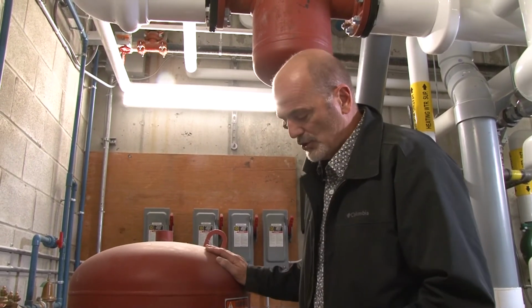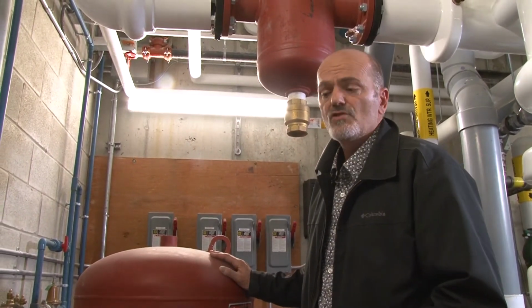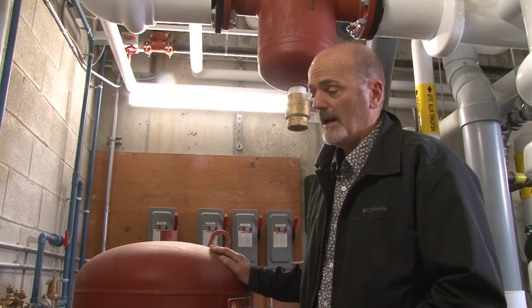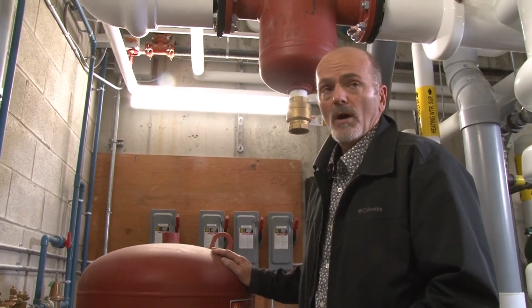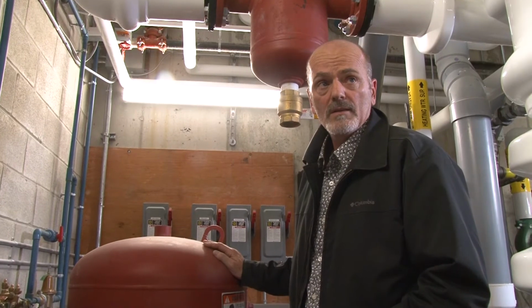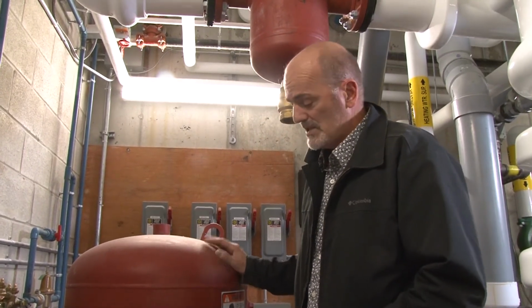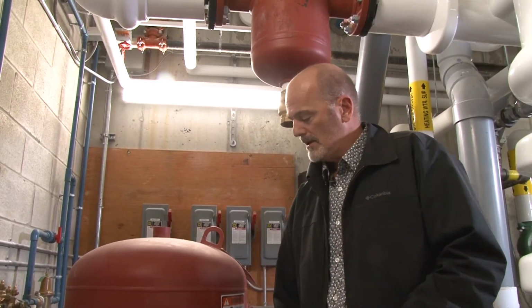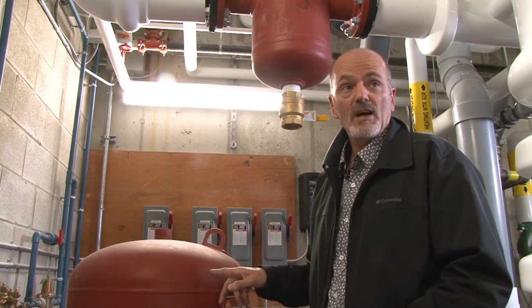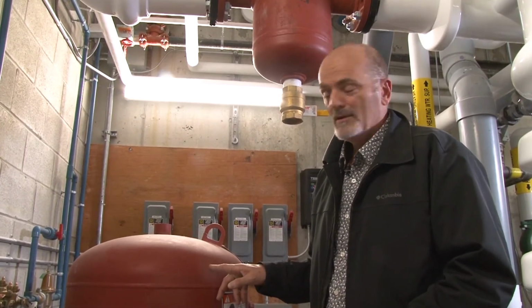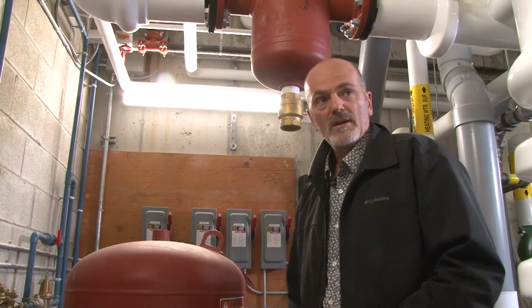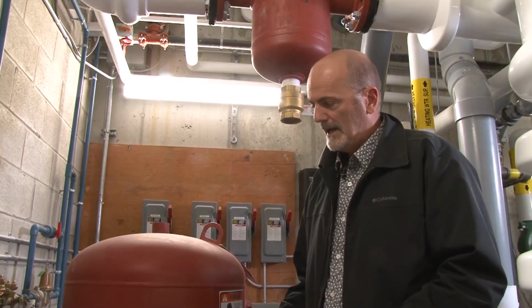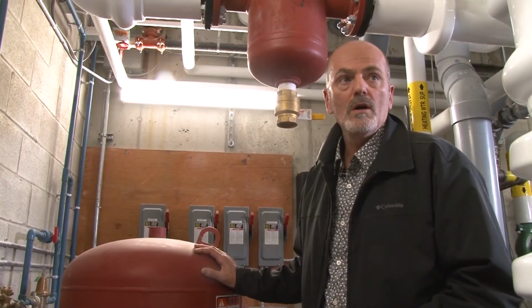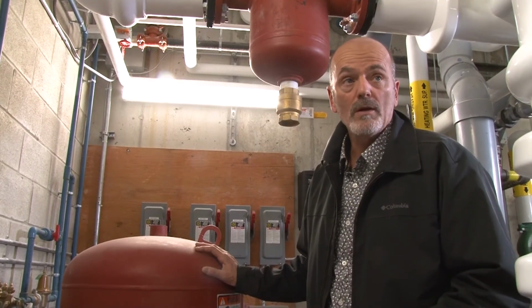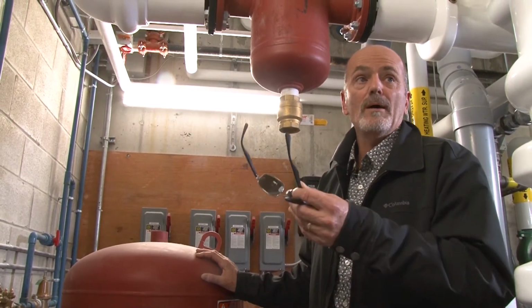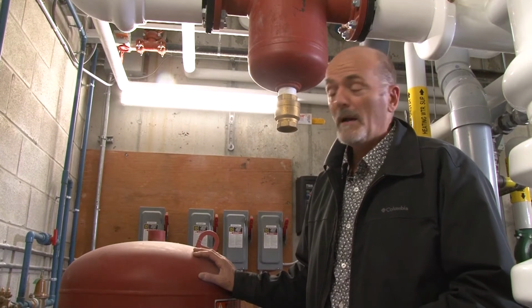If you have an issue with the tank, and this is really the only issue that will happen with these tanks, you get a rupture or tear or a leak in the bladder. What happens is the system fluid goes in to the secondary side where the air is, pushes the air out of the tank, and now we have no cushion and no bladder anymore. So the next time the system heats up, fluid starts to expand.